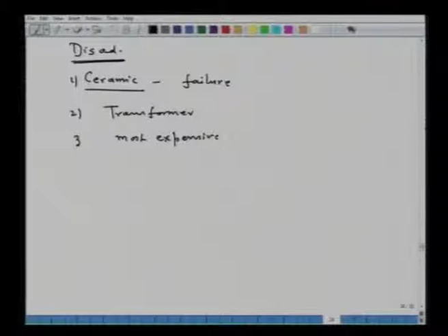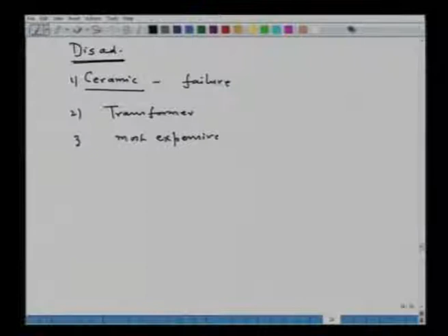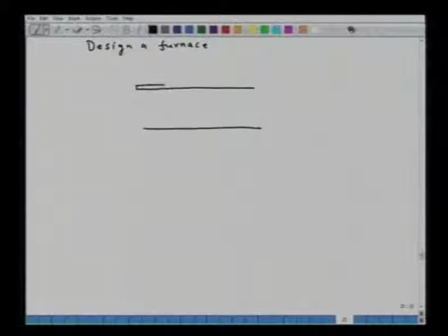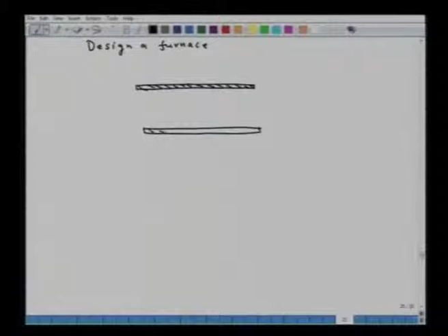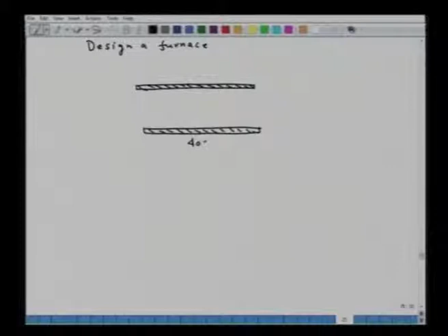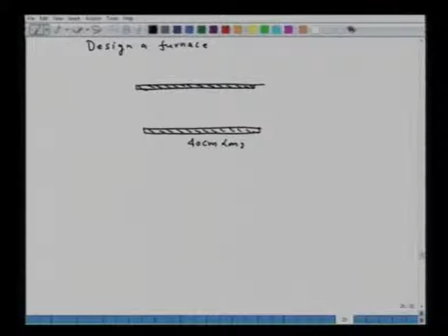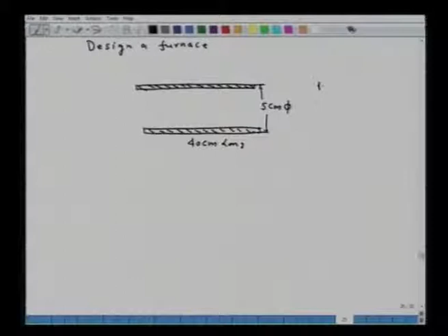Now, in brief, I would like to illustrate what is required when you want to design a furnace, for example a laboratory type of furnace. Take a ceramic tube, 40 centimeter long, with an outer diameter of 5 centimeter. We want to design this furnace to operate at 1000 degrees Celsius, operated at a 220 volt line, and the line has a 5 ampere current socket.